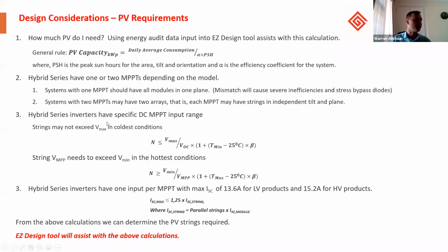The hybrid series inverters have very specific DC MPPT input ranges. So the EZ Design tool does these calculations in the background. The number of modules you can have in a single string is determined by this equation here, which does the temperature correction for the coldest conditions. Again, we also need to consider that the MPP voltage of the string needs to be within the MPPT range of the inverter, and that is then determined by this equation here. So you'll have a maximum number of modules and a minimum number of modules to work with. But again, the EZ Design tool does this for you.